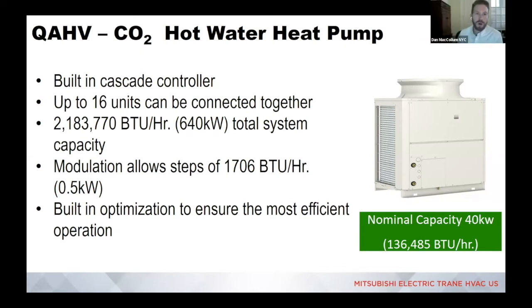So the only system that we talked about utilizing a storage tank for is what's up on the screen right now, the domestic hot water heat pump. Yeah. And that's a high delta T system that you're not going to want to use for space heating. So the domestic hot water heat pump should only be used for domestic hot water heating or other high delta T applications. The unit that I kind of gave a teaser about, that works in tandem with the domestic hot water heat pump.